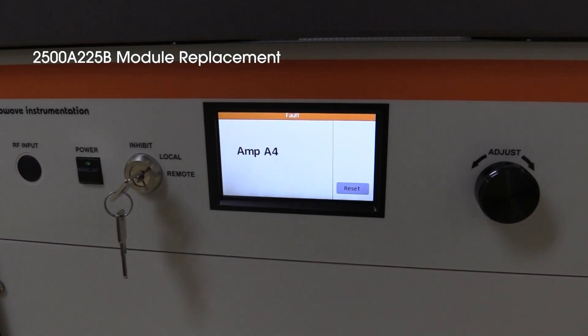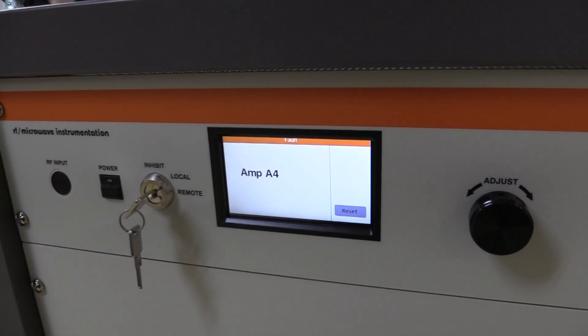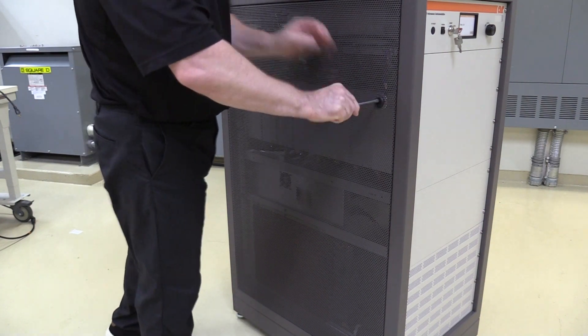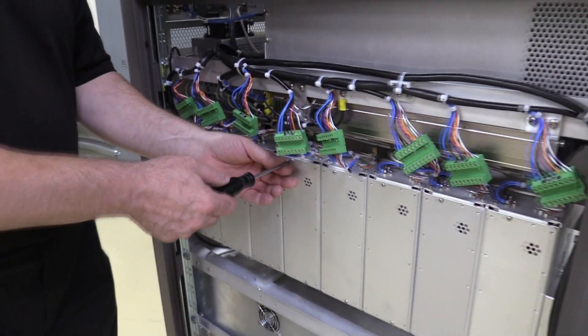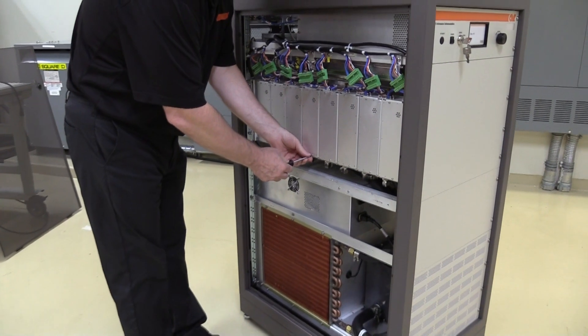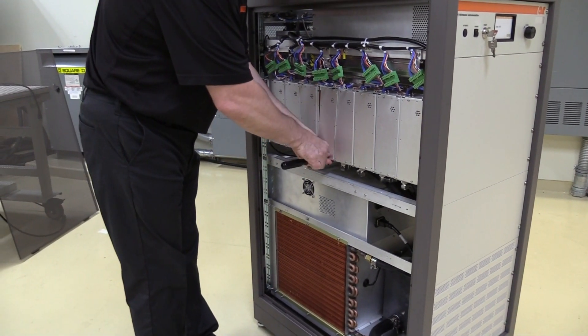In the event of an RF module failure, you will be notified by the front panel display. To replace the module quickly and efficiently, simply remove the side cover. The failed module, which is identified by the front panel display, can also be confirmed by the red fault LED seen through the top cover perforations of the module.